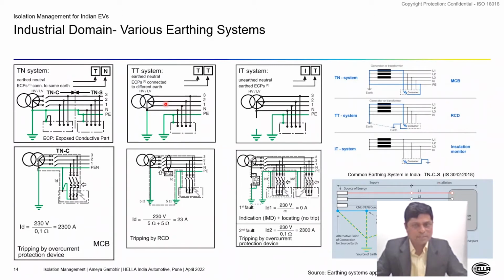So we have three major systems in the world: the TN system, the TT system, and the IT system. These systems basically describe how we receive electricity in our households from generators, distribution, and other systems. For example, the first letter in TN or these systems talks about the neutral terminal, whether it is directly earthed. If it is directly earthed, it is called T, and if it is not directly earthed, it is called I.